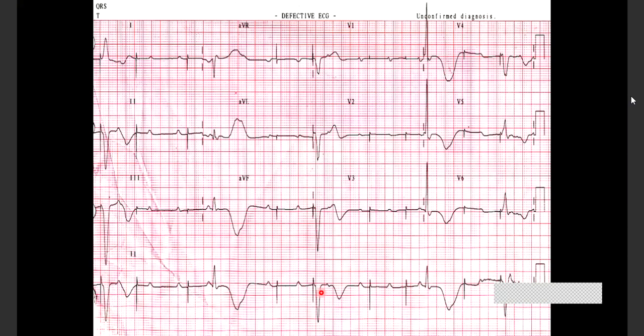It won't be 70 or 60. It will become very much less. It may become 50, 40, and irregular. So suppose you have a battery problem and it cannot generate a voltage, then obviously the voltage will be substandard to produce a capture. So you will have a loss of capture in a lead problem, and also in a battery problem. If the battery doesn't generate enough threshold, enough voltage, you're not going to have a capture. So that's why you have loss of capture. Loss of capture is absolutely right. But the loss of capture here might be because of a battery problem.